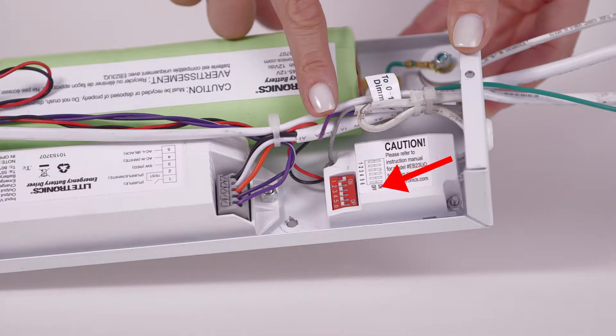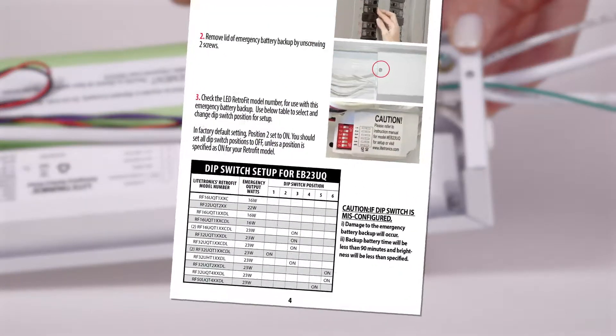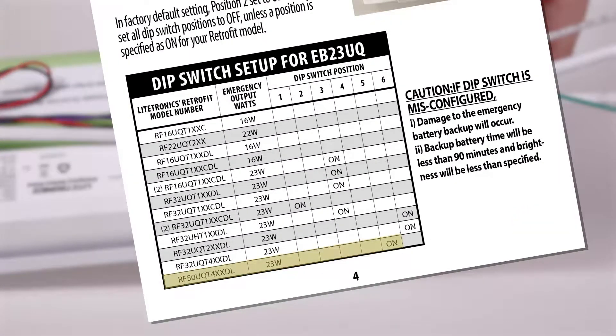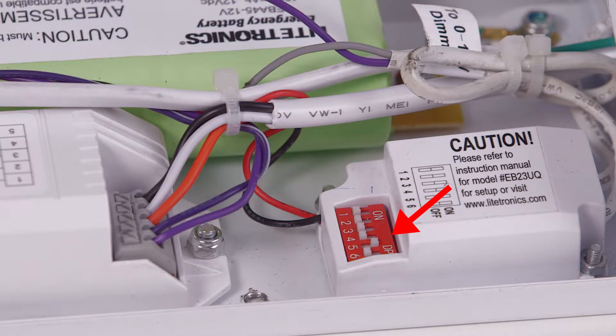The dip switch is located inside the EB23UQ unit. Select the matching dip switch setting from the installation manual. In the factory default setting, position 2 is set to on. We will turn that off and switch on position 5.